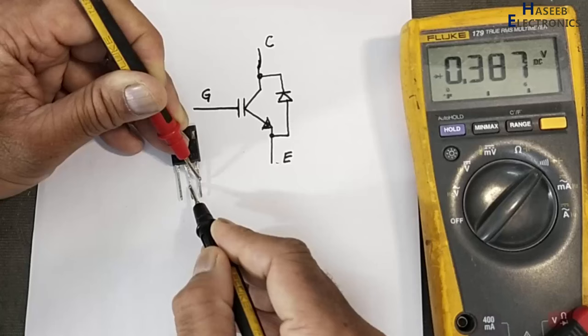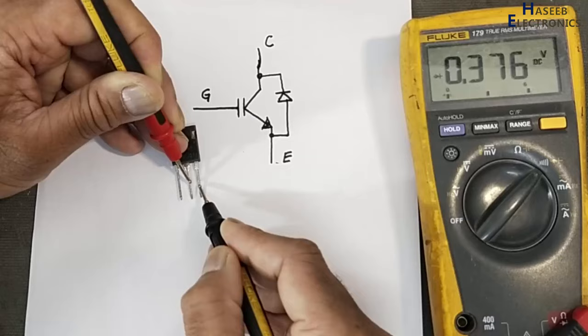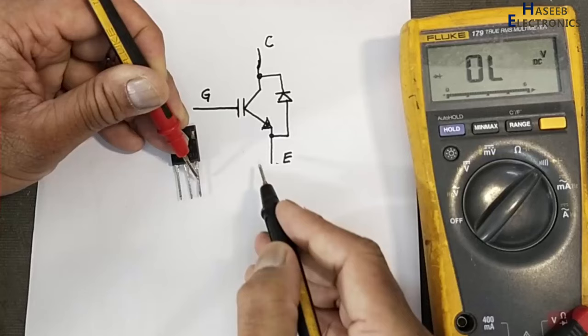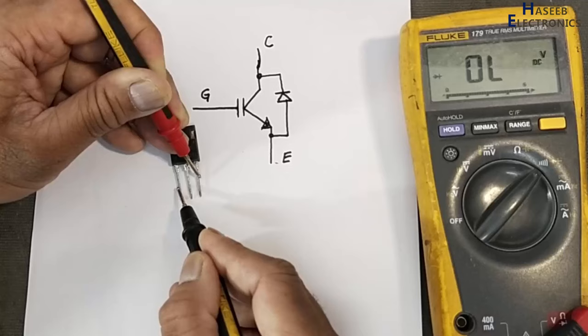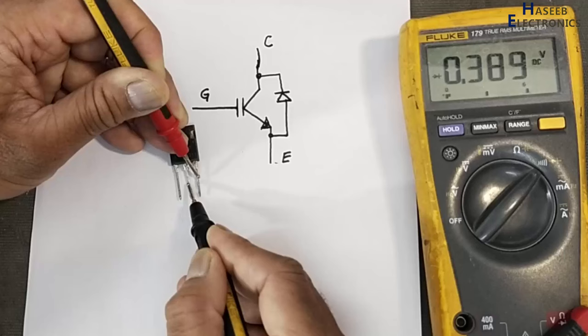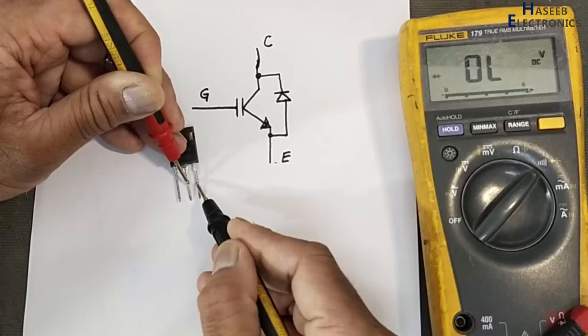This is one condition. This is second condition from here to here. Now red lead at emitter, we will discharge the gate now. Black lead to gate, now return back to collector—0.389. Swap the leads between emitter and collector. Now it is open, so it is good IGBT.